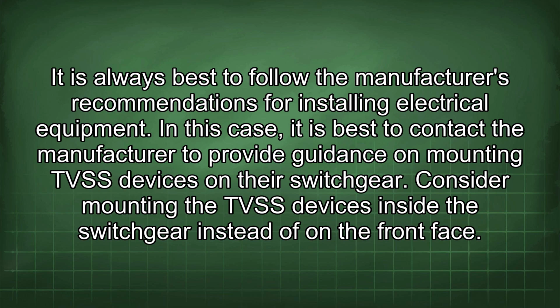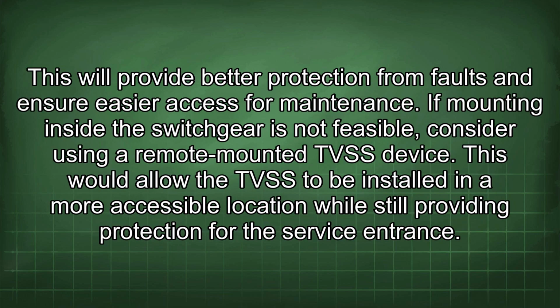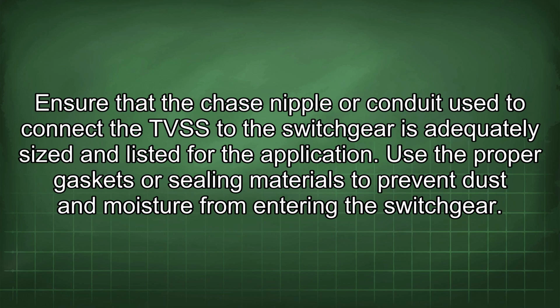Consider mounting the TVSS devices inside the switchgear instead of on the front face. This will provide better protection from faults and ensure easier access for maintenance. If mounting inside the switchgear is not feasible, consider using a remote-mounted TVSS device. This would allow the TVSS to be installed in a more accessible location while still providing protection for the service entrance.